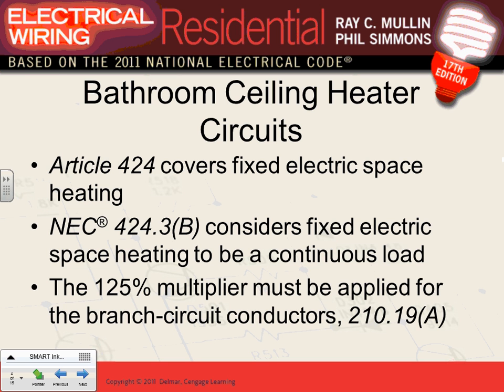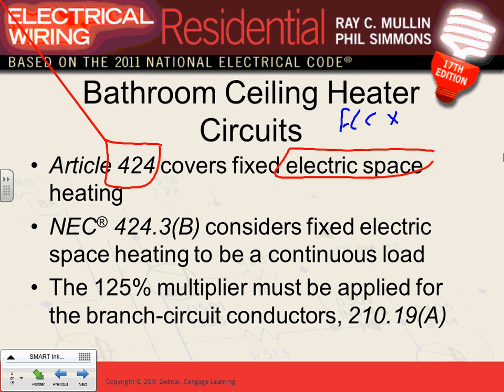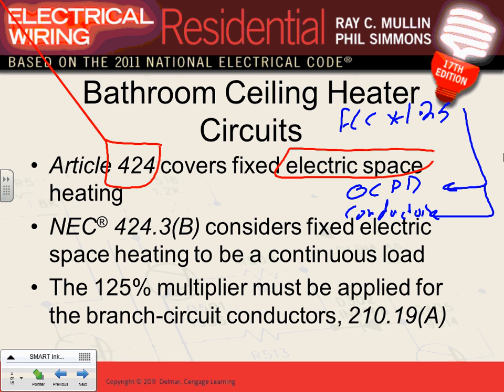We have a whole article, guys, that talks about fixed electric space heating. I want to summarize this article for you in two things. When it comes to heat, very simple, two things. If you take the full load current of the heater, multiply it by 1.25, and from here you can size overcurrent protection device and also conductors. Done. That's what this article summarizes as far as we're concerned, right?